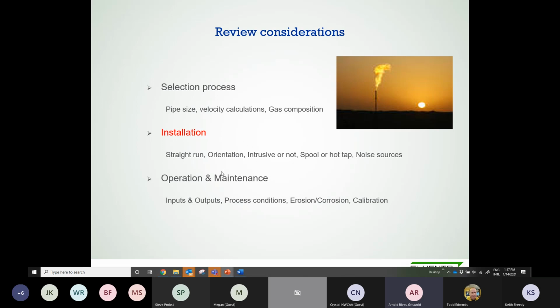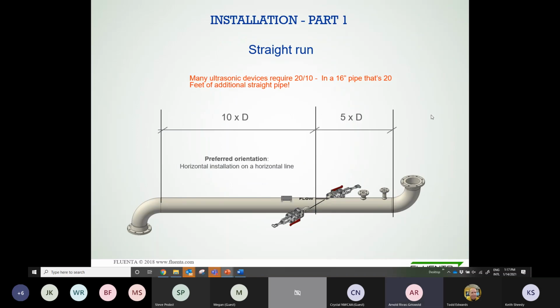Okay. So in terms of the installation, there are different considerations: straight run, the orientation, the decision whether or not to use intrusive designs for the sensors, whether you need a spool piece or you're going to do a hot tap installation, and then sources of noise. You have to think about that as well. So straight run, like any particular meter, you need a certain straight run to make sure that at the measurement point you have a fully developed flow profile, or as good as possible, right? So many ultrasonic devices normally require 20 diameters upstream and 10 diameters downstream. I'm sorry, and in our case, we focus on 10 and 5, which is half of the original requirement.